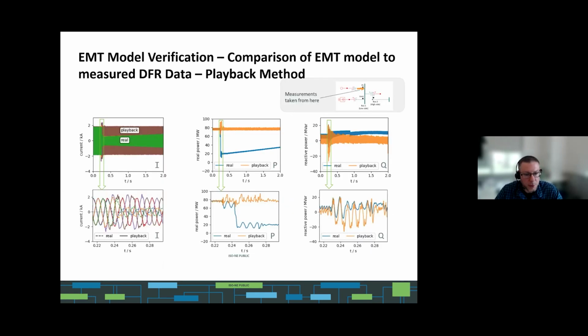More on the real world example here, and why we think EMT studies are very important for reliability of the system. This is an example of an actual disturbance that happened on our system up in Maine. There was a breaker with low SF6 that opened unexpectedly, and this resource, a solar plant, reduced its output by roughly 80%.